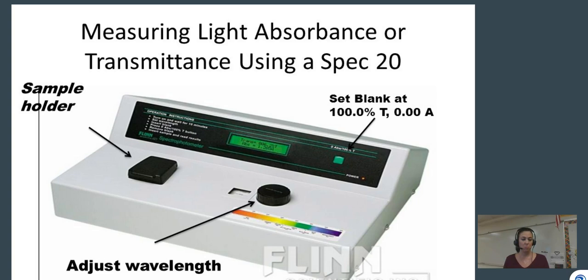Blanking sets the machine to 100% transmittance for that cuvette, or zero absorption. Remember: if all the light is going through, 100% is being transmitted, which means zero light is being absorbed.